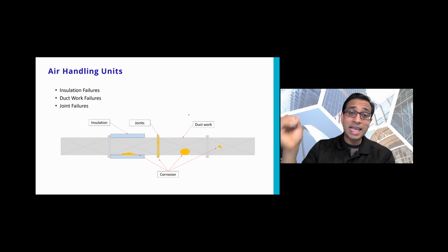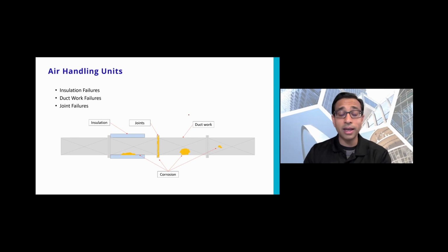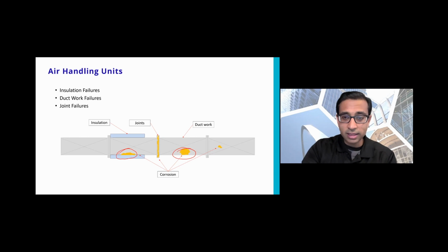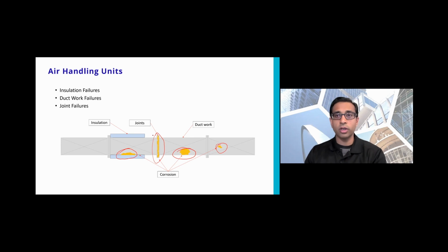The problem makes its way to the ductwork. I know people use stainless steel ductwork and all that, but that's still going to end up rotting through—I've seen it a million times. You'll start seeing corrosion in the various areas underneath the insulation, then it hits the ductwork itself, and you start seeing failures in the joints and holes in the ductwork.